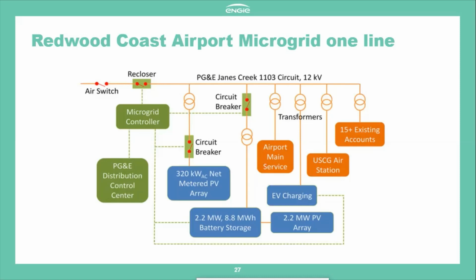The microgrid controller will disconnect from the grid and then manage all of this power. The battery storage system, which is 8.8 megawatt hours, and the solar, which is 2.2 megawatts, isn't enough to manage the entire load. So part of what the microgrid controller will do is lower or reduce the load on some of the existing load centers, prioritizing accordingly.